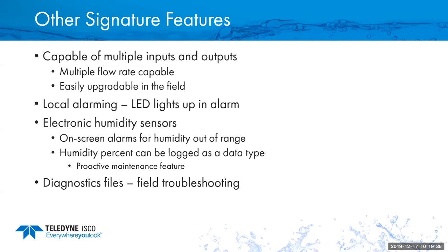Local alarming: there's an LED on the front that lights up when the unit goes into some alarm conditions that you have set. Also, we use humidity sensors to measure the humidity. If somebody leaves the box open or something cracks and you get an intrusion of humidity, we'd be able to let you know through looking at the data or setting those up as alarms. Diagnostic files: you're able to troubleshoot via downloading some files, pulling the DDP file, which is the data protocol for pulling the data out of the signature flow meter and putting it into the FlowLink program.